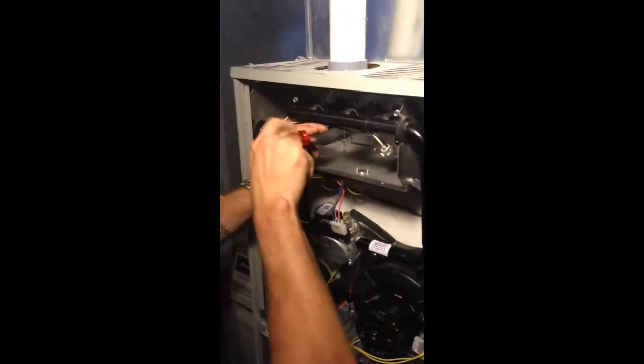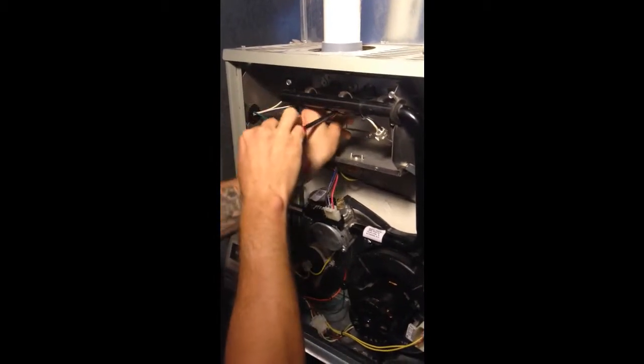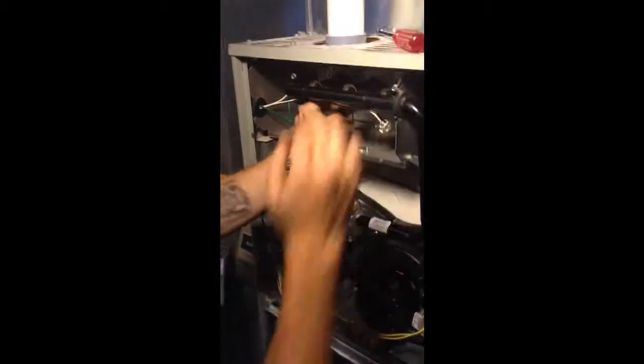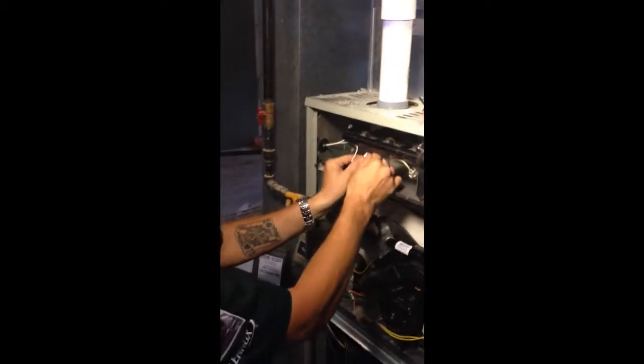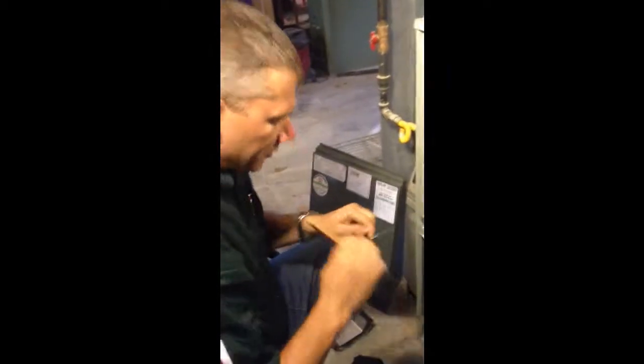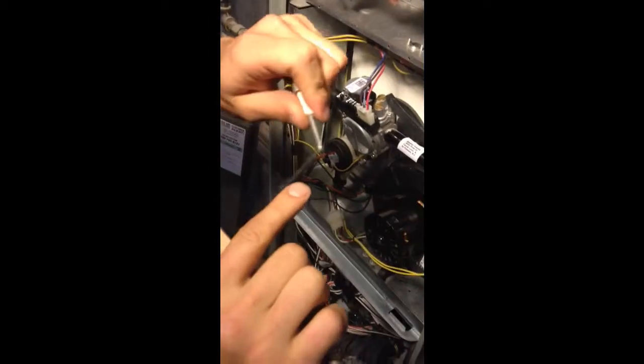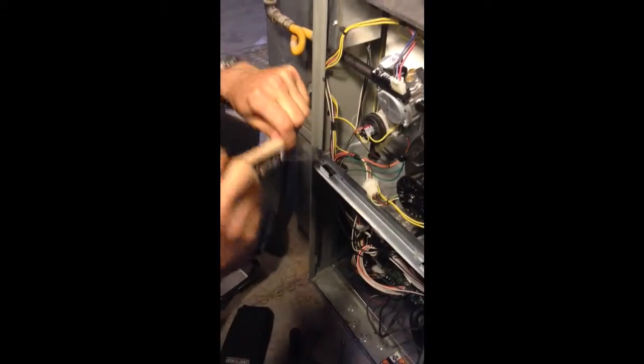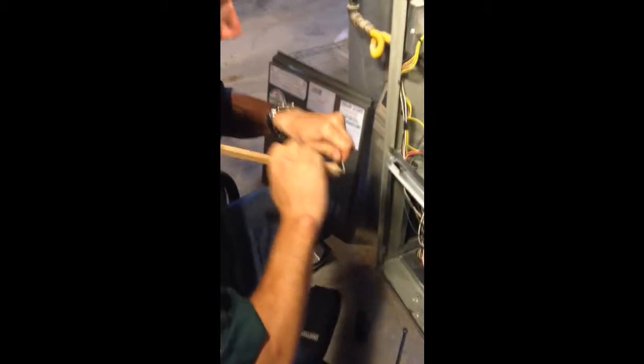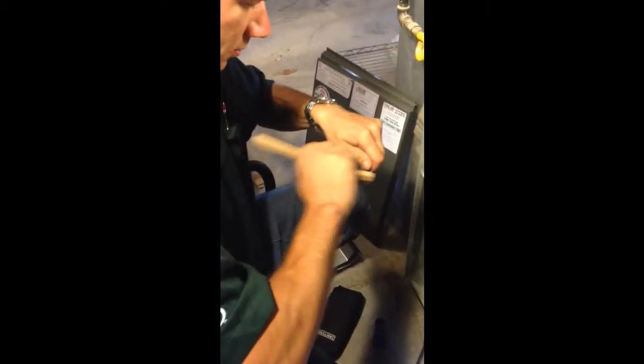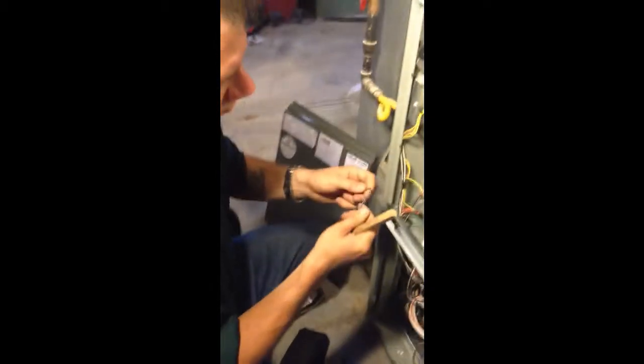So now I'm going to pull the flame rod. I just cleaned the burners. I'm going to pull the flame rod out. And it looks exactly like it sounds. It's just a rod. And then we make sure to get, you can see the black on there, the corrosion buildup. So we clean that off. That's because fire's getting shot at it. I want to get all that cleaned off as much as possible. And still dark, but it's not, you know, coated.